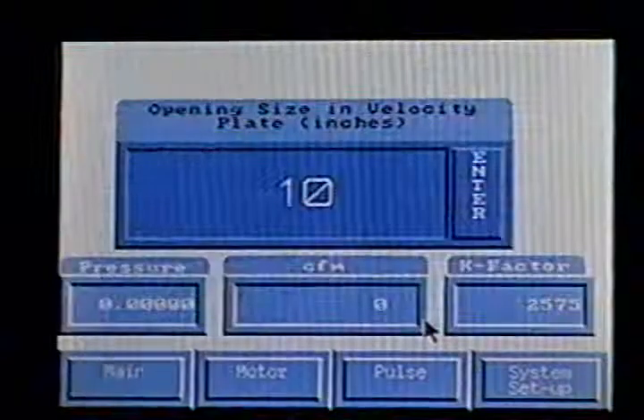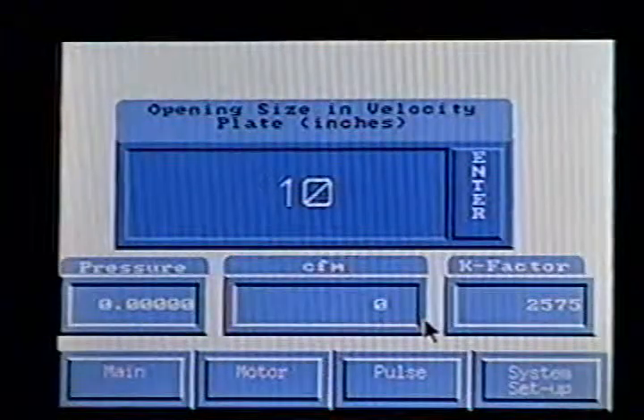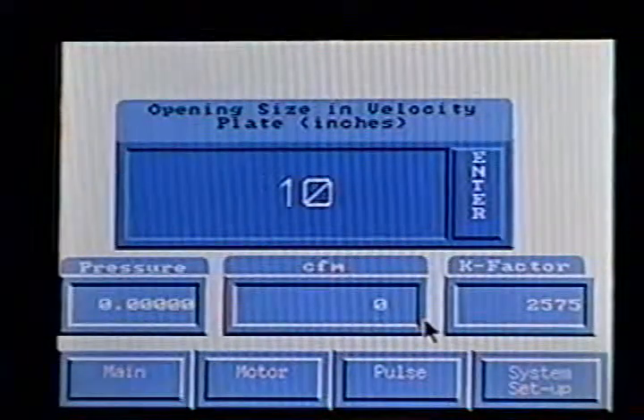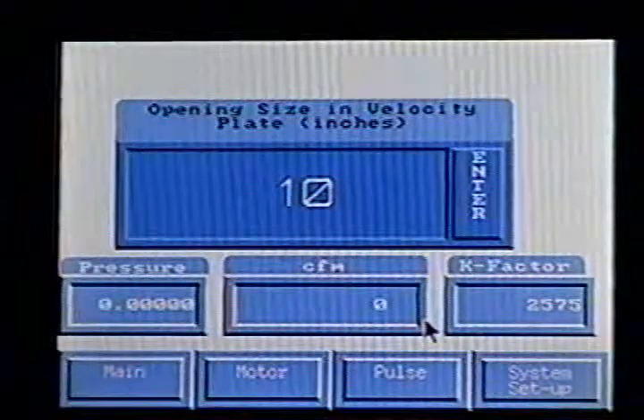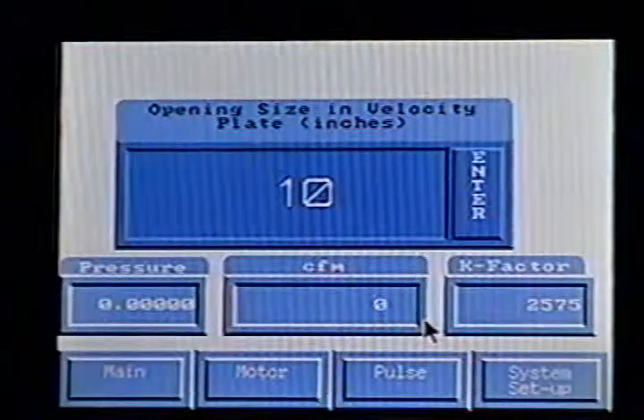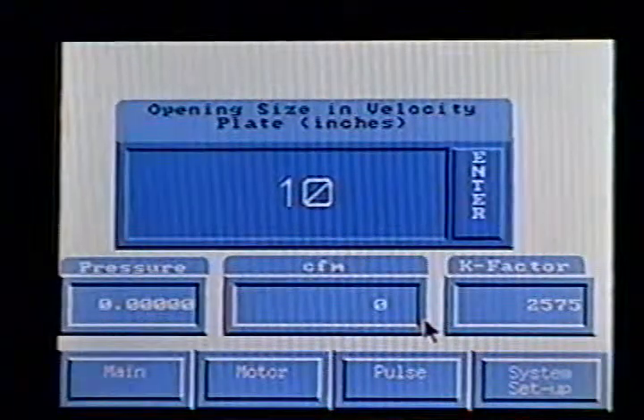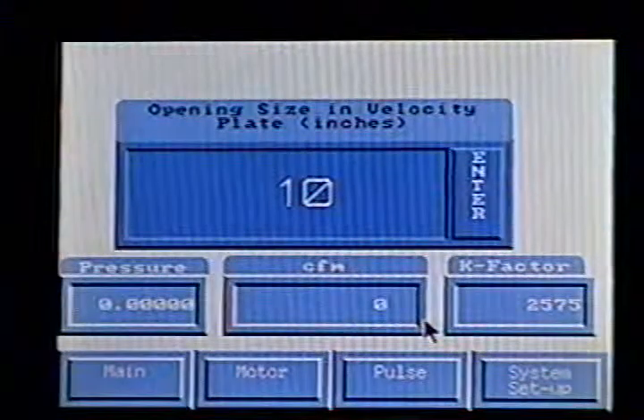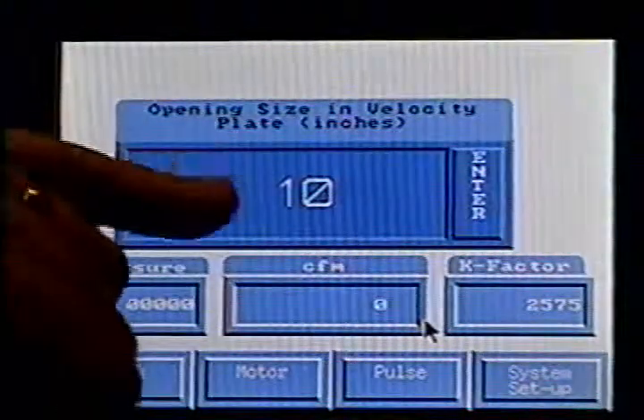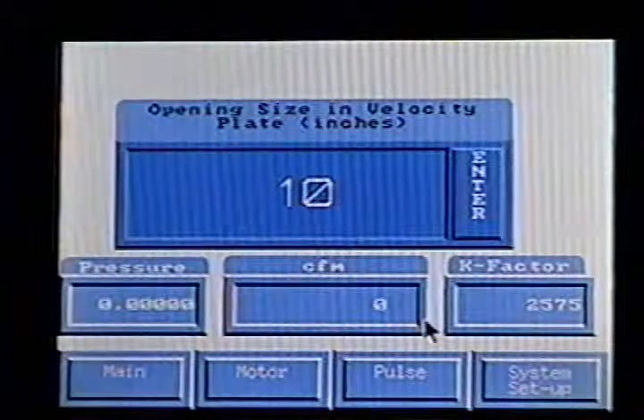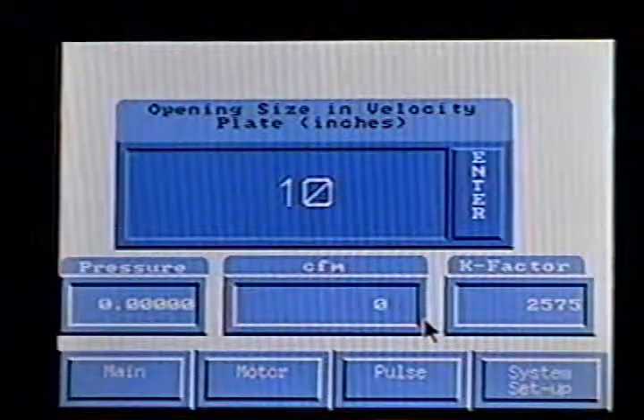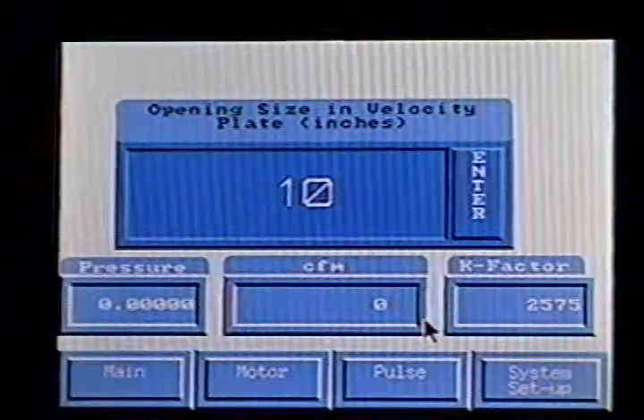The last thing on here is the orifice plate. Again, I'm talking about what's back behind the collector in the ductwork. There's that big round circle. That's the orifice plate. The way we're measuring the CFM is the resistance through that orifice plate. You come in here, you tell it it's a 10-inch orifice plate. You can put in whatever number you need based on the ductwork size you're utilizing, but that's how it determines CFM.